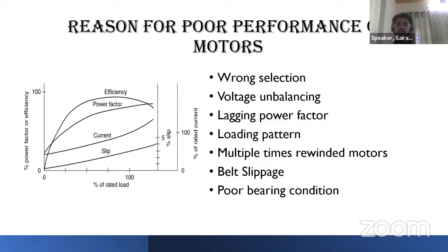The reason for poor performance of motors will be mostly wrong selection, like the higher capacity selection. We will be selecting higher capacity, or going for lower capacity selection and overloading the motor. Then voltage unbalancing, a lagging power factor. This will cause the I square R loss to increase. Then loading pattern. If the loading pattern is huge, then we have to assist it with the help of a VFD drive so that the operation will be effective.